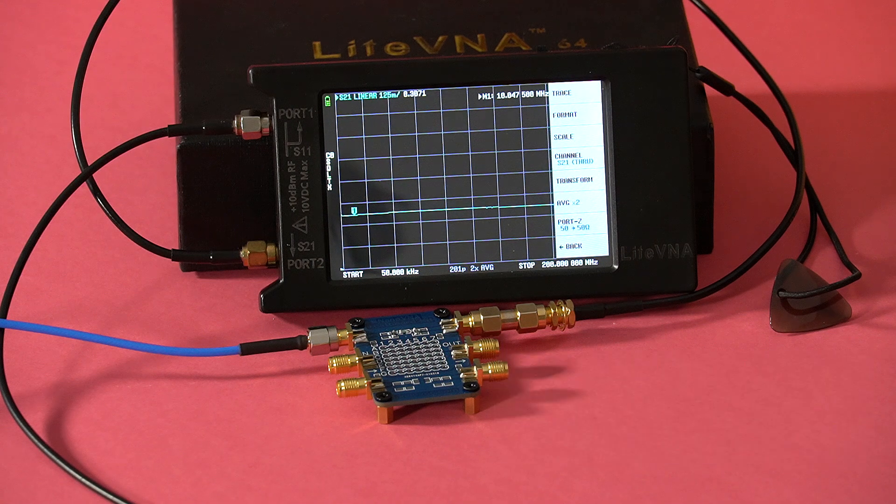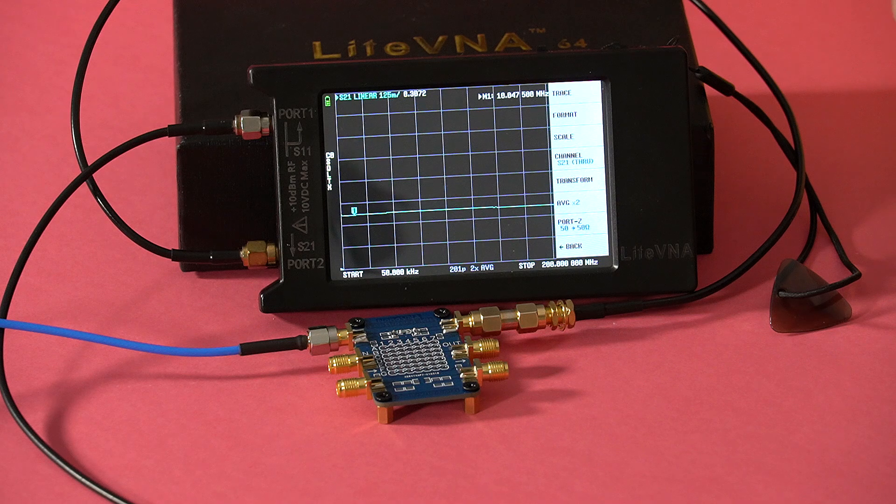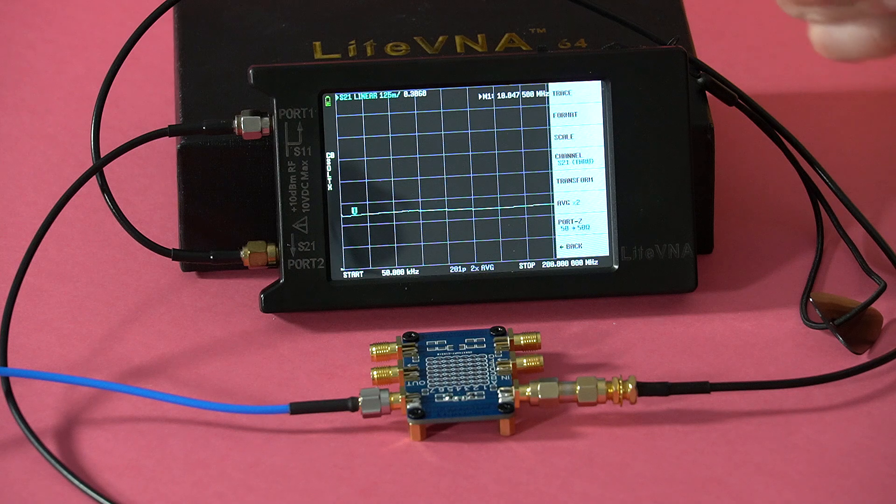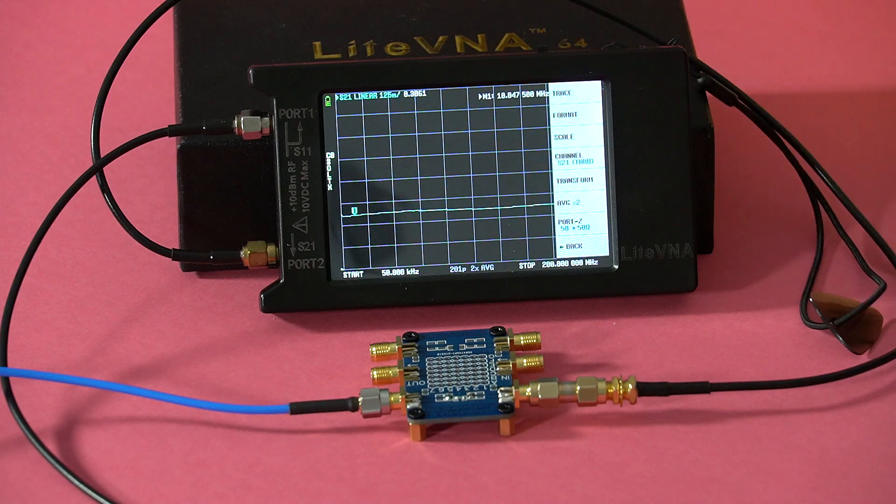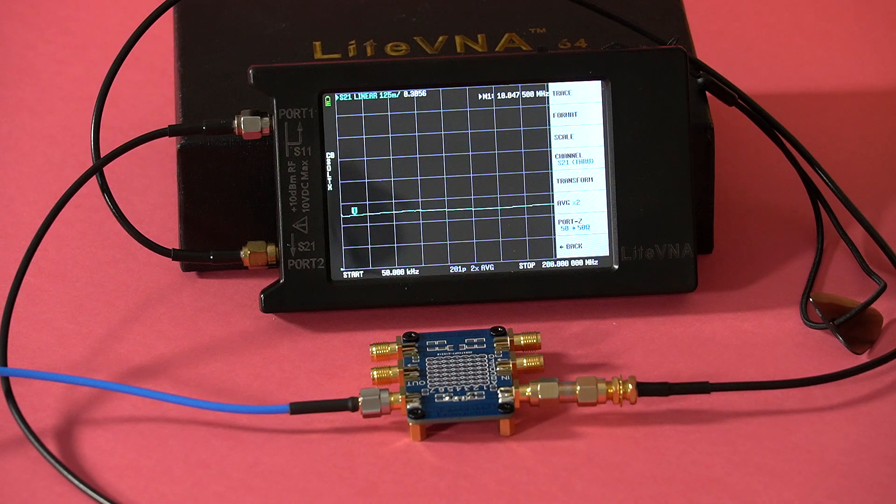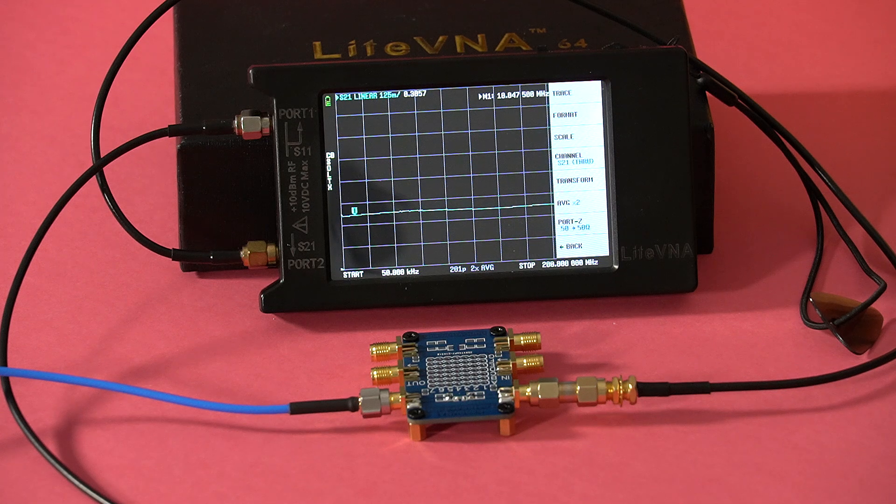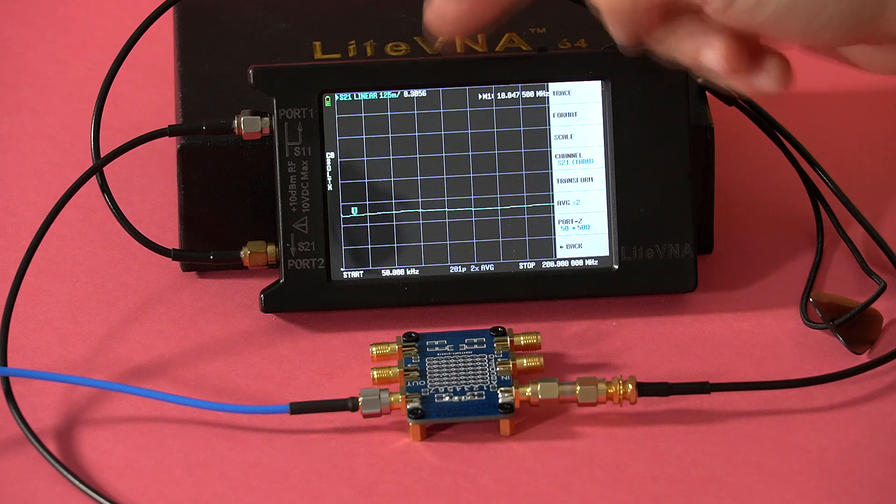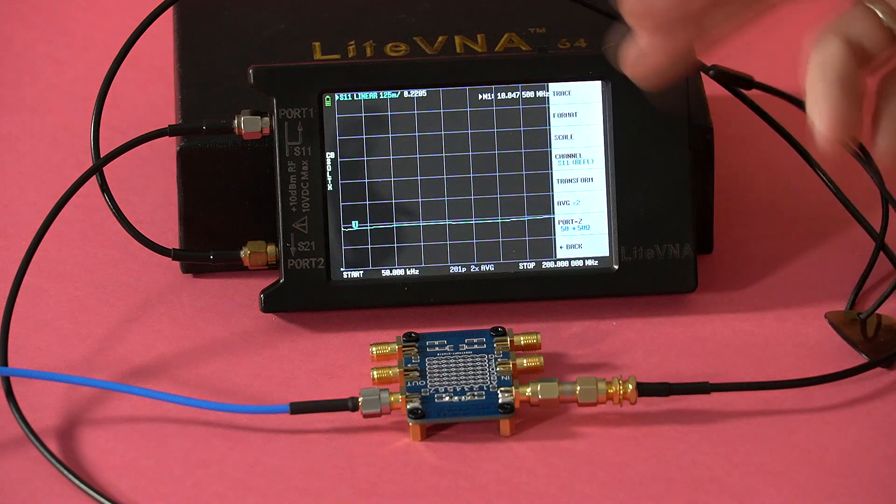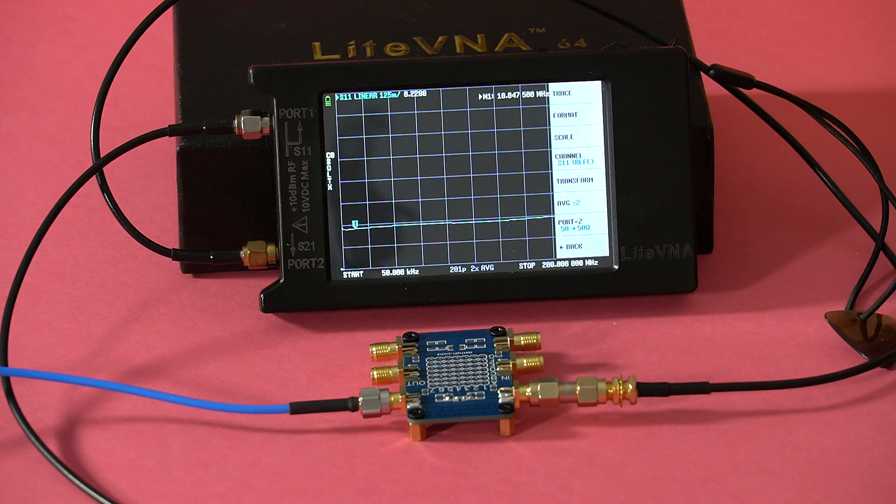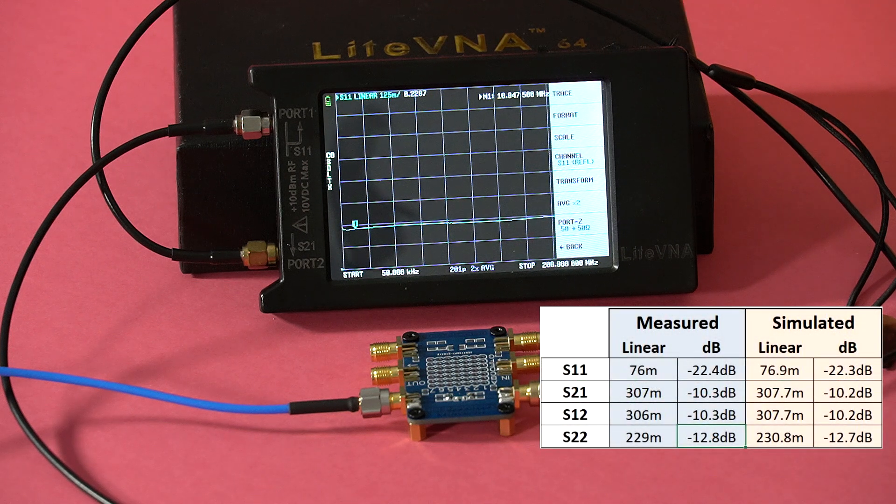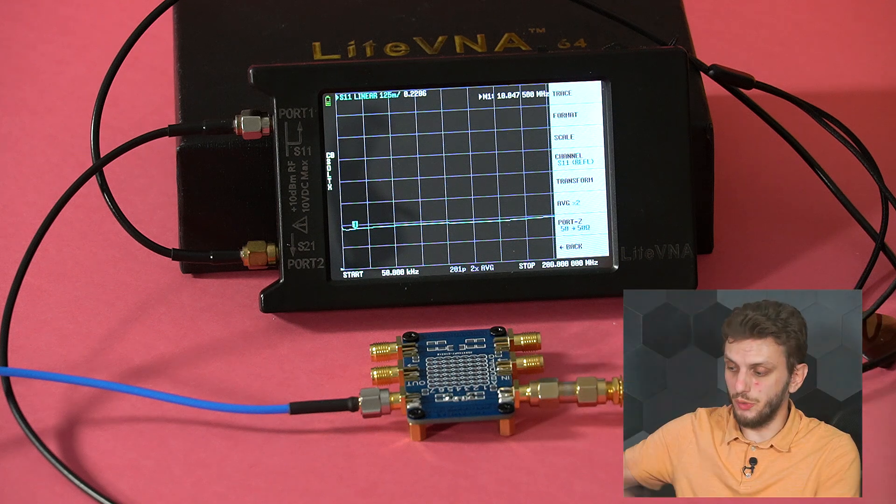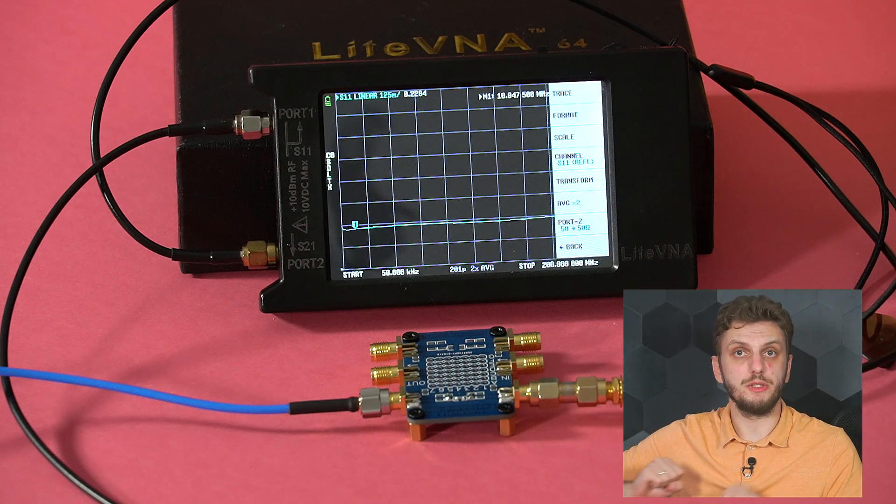And now, to get the other two S parameters, I will simply rotate the circuit. So I've swapped the connections, and now the two ports of the circuit have been interchanged. So right now, when we're measuring the S21 parameter, it's actually the S12 parameter, but for the circuit put into the other way. So for this parameter, we're getting the same 0.306 value. And if we now go to the reflected value, so the S11, which is S22, for the circuit in the other position, we're getting a value of 0.228. So decently close values to what we were getting in the circuit simulator. So this way, by rotating the circuit, we can obtain the full S-parameter matrix.